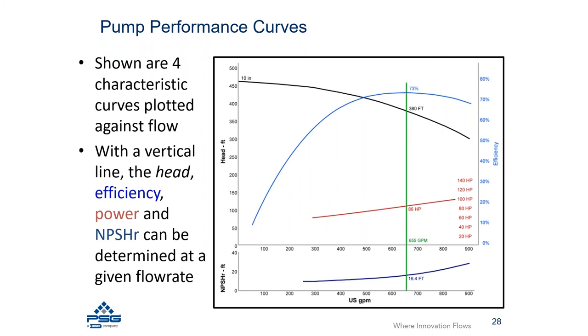In general, if you move to the left of a centrifugal pump curve you will see higher heads, lower horsepower, and generally lower NPSH requirements. The efficiency may get better or worse depending on whether you are to the left or right of the best efficiency point.